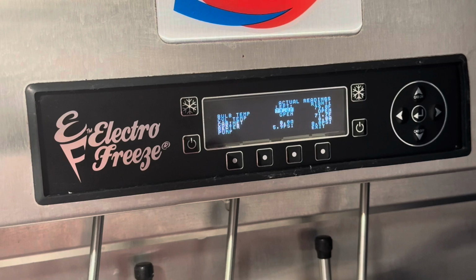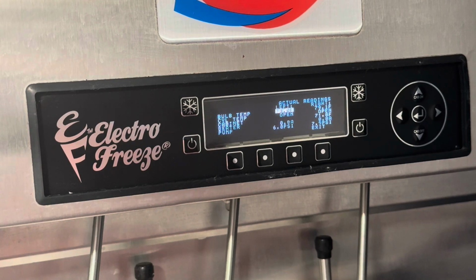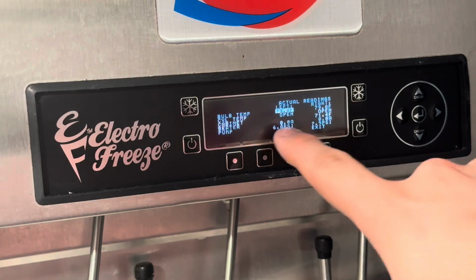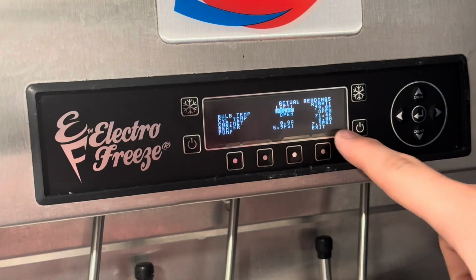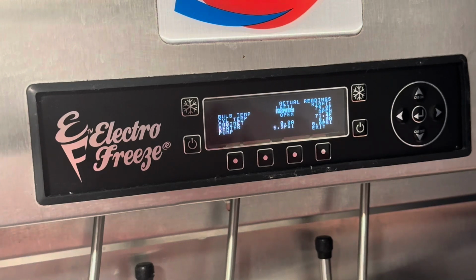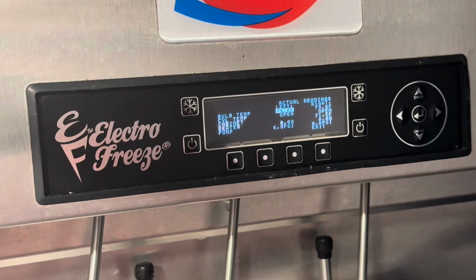You can also see at the very bottom line the PSI, that is our pressure switch. Now these machines sometimes from the factory come with transducers, so they read actual pressure, but nowadays they're just normal pressure switches which are either open or closed. So this will read whatever reads down here, something like this, and then it'll read about 43 PSI and shut off. That is not an actual pressure reading, that's just the way ElectroFreeze made these machines. So that's about it for this menu here.